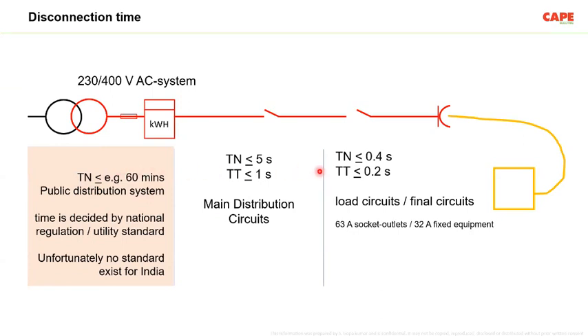The maximum allowed times in the final circuit are 0.4 second in case of a TN system and 0.2 second in case of a TT system. At the main distribution circuits inside the consumer premise after the meter, it can be up to 5 seconds in case of a TN system, or less than 1 second in case of TT. These disconnection times are applicable for up to 230 volt.